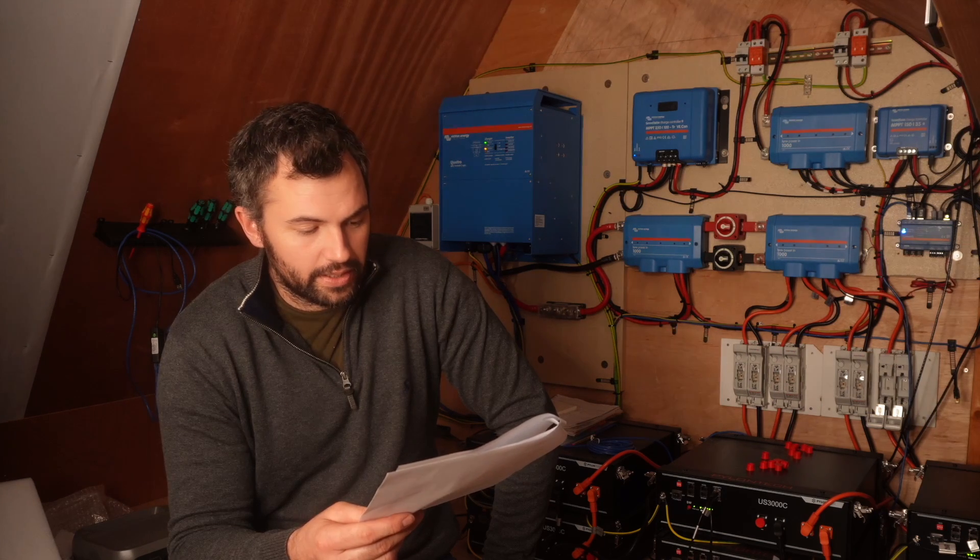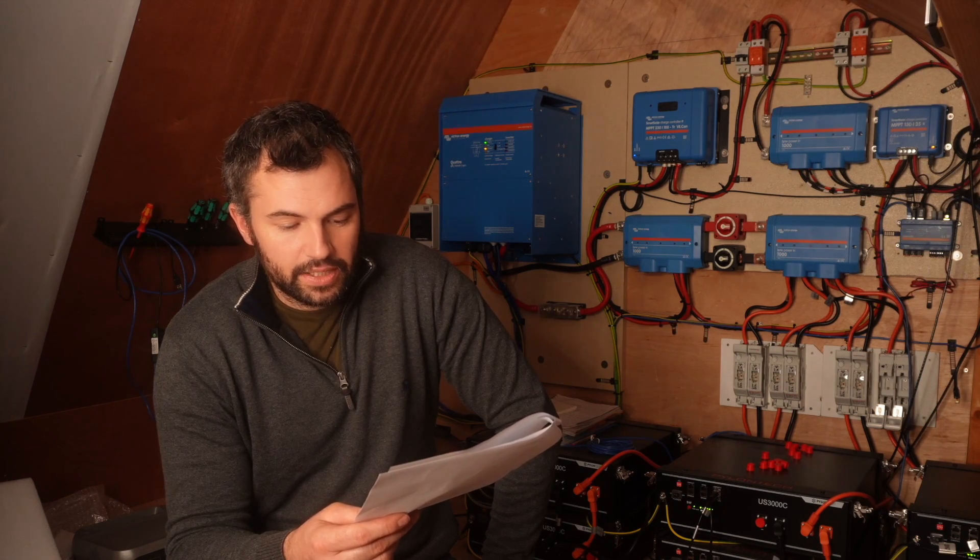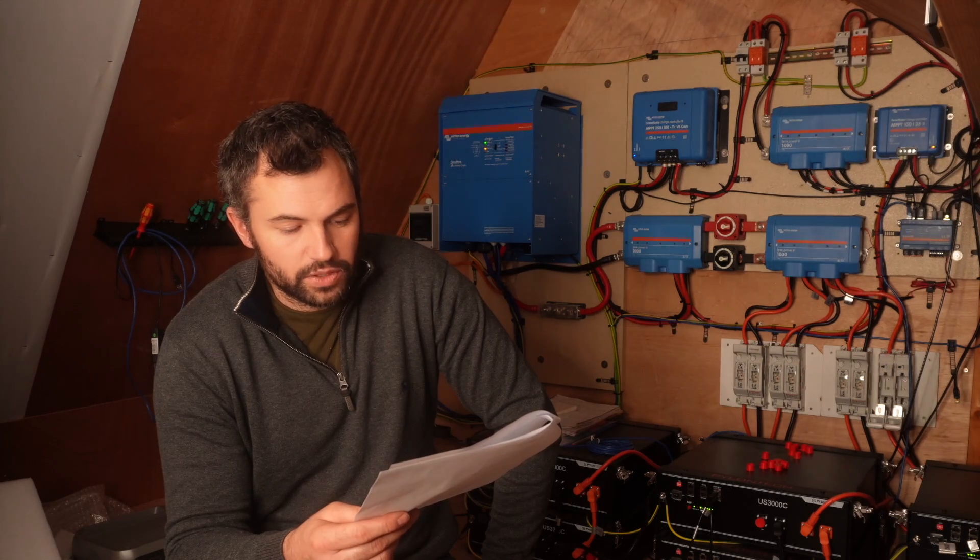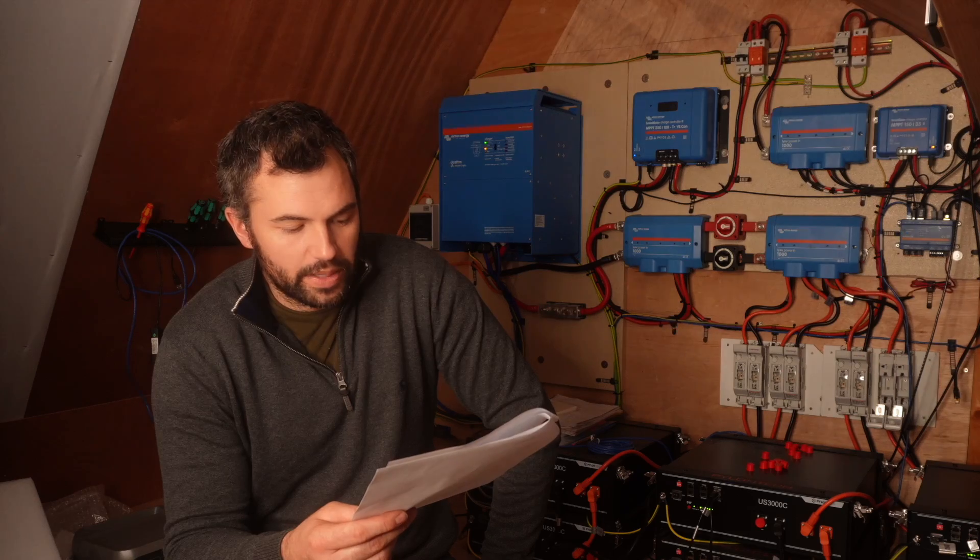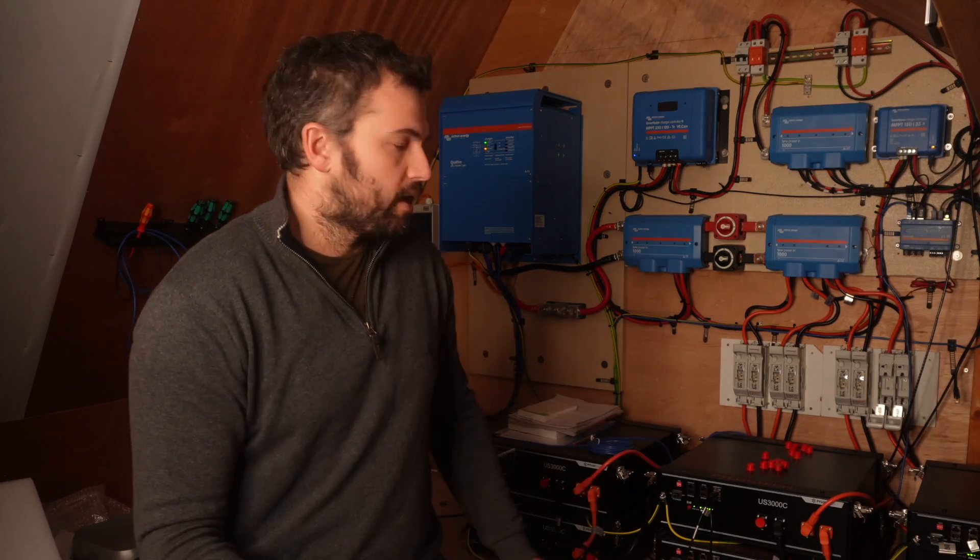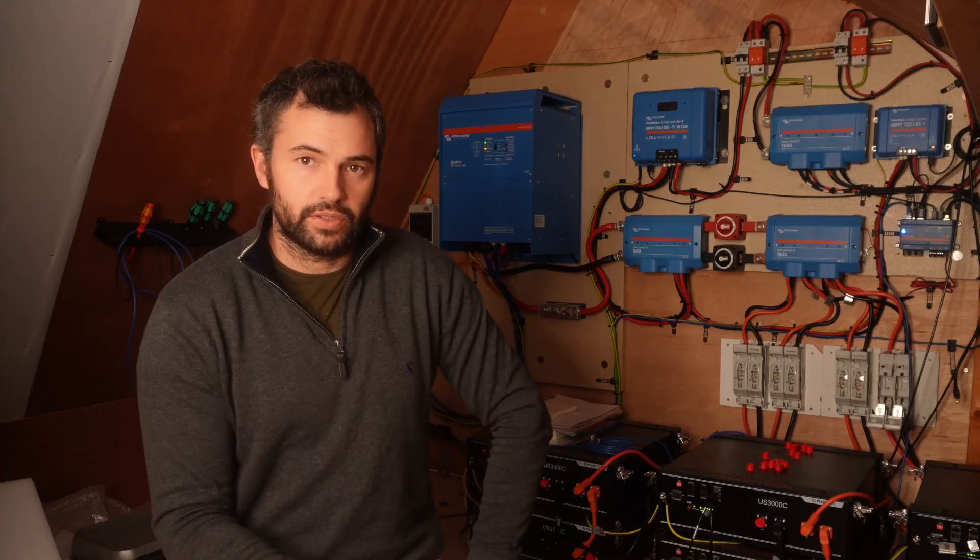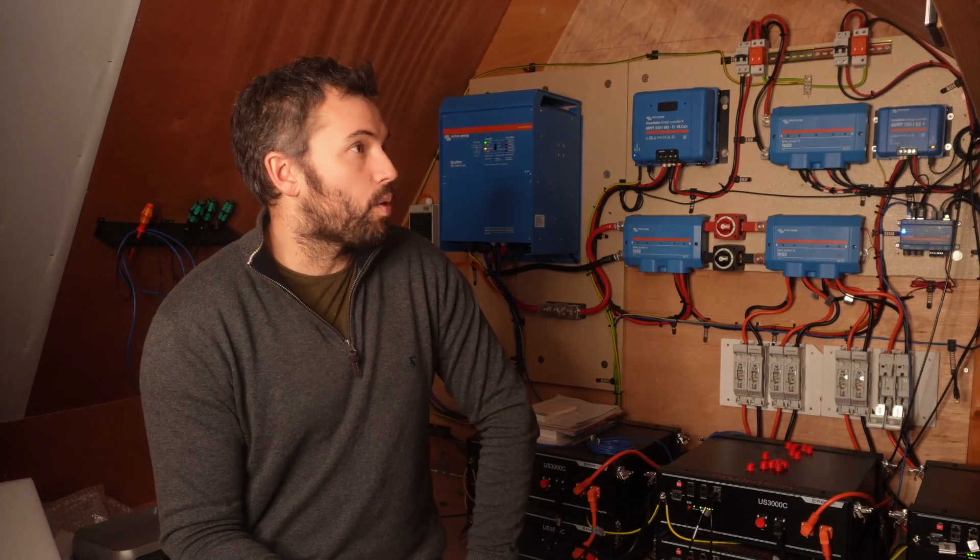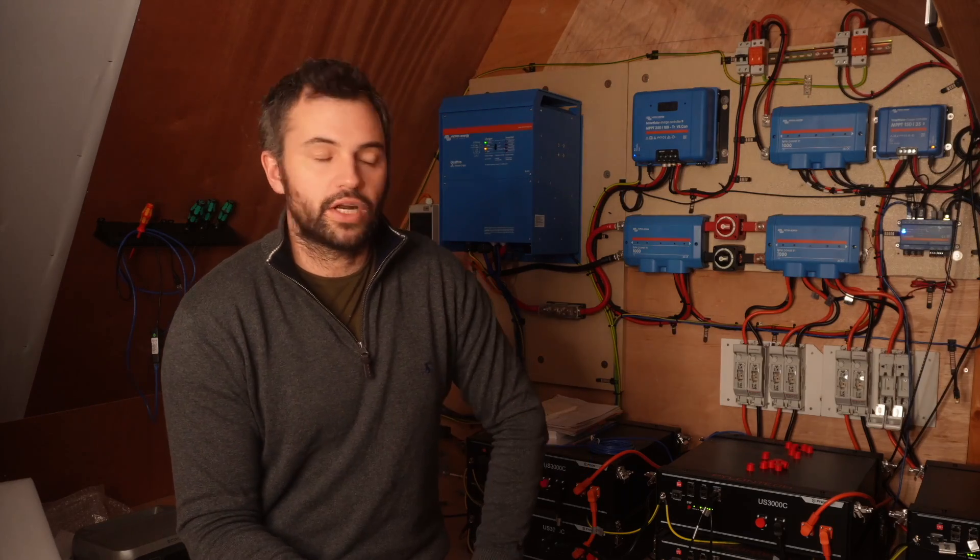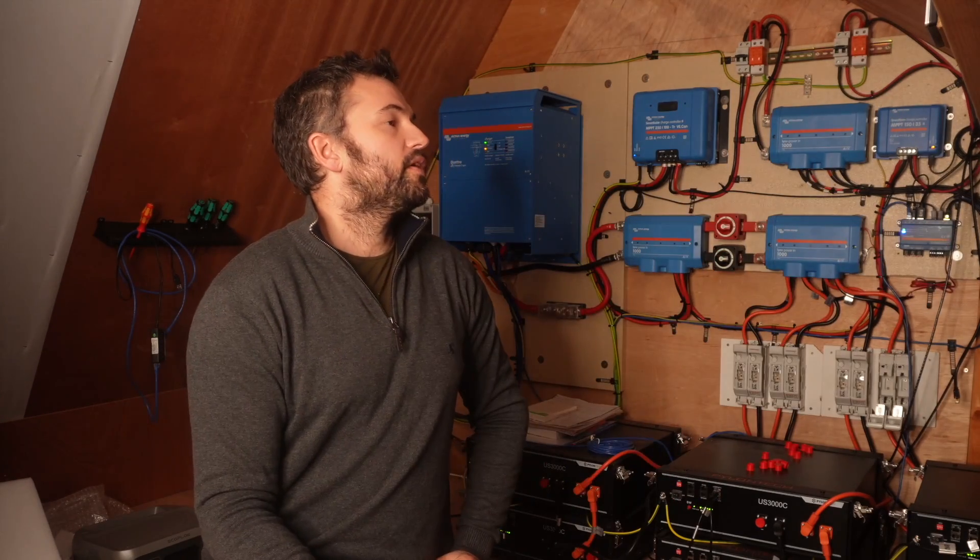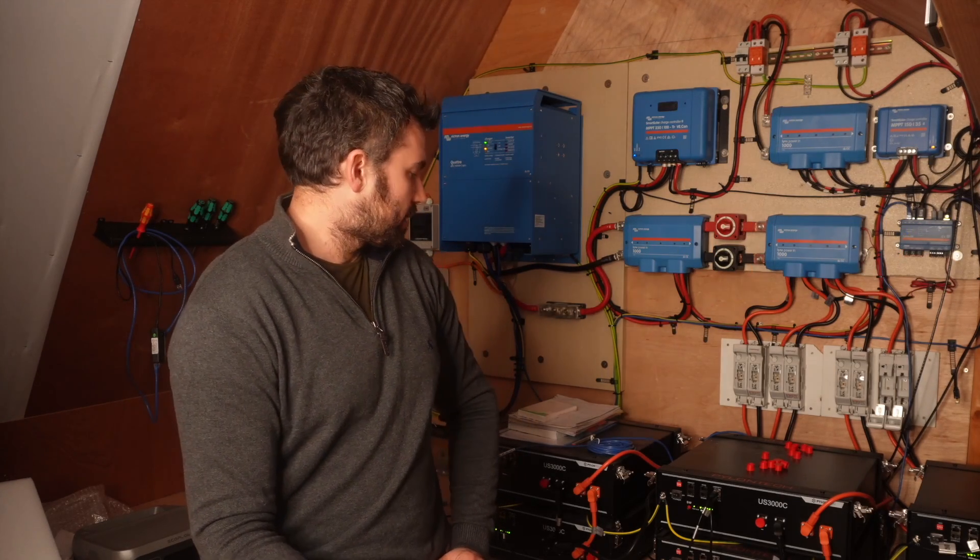All working okay. If this battery is connected to others as part of a stack and not a standalone, please charge all batteries including this one to 100% SOC individually before connecting together so all cells are balanced to avoid error codes and alarms when reinstalling. I know all these are already balanced because we've already done battery view and these batteries are working perfectly. So I'm charging them to 100% now together. Got 31 watts left to put in them so they are fully charged.